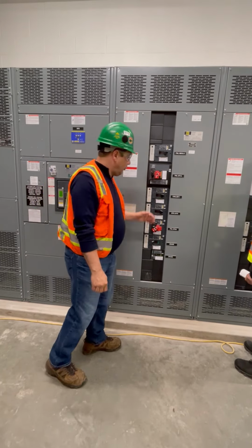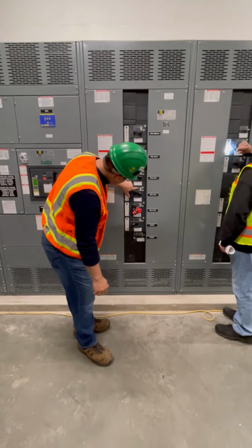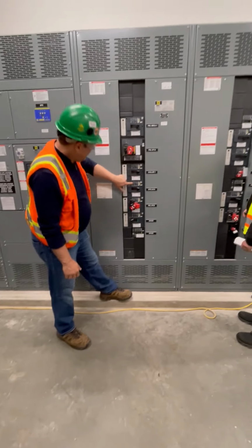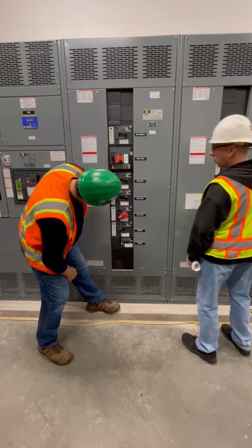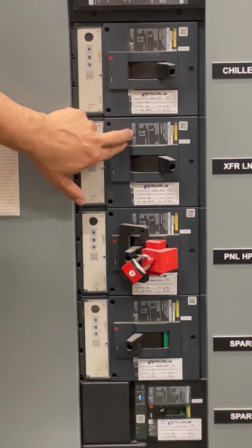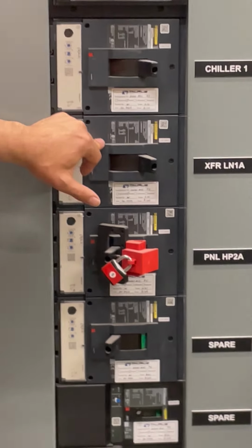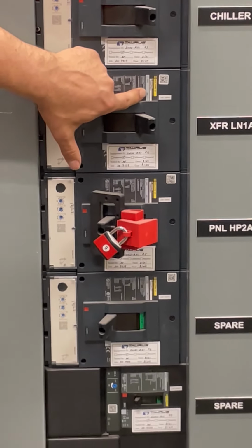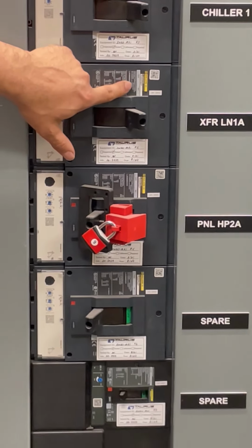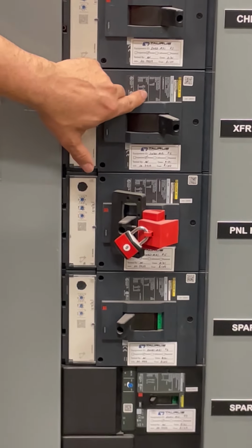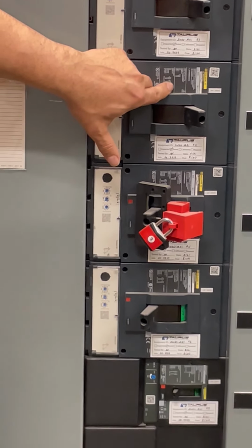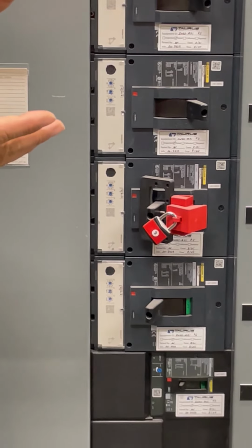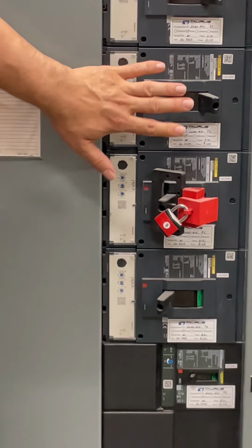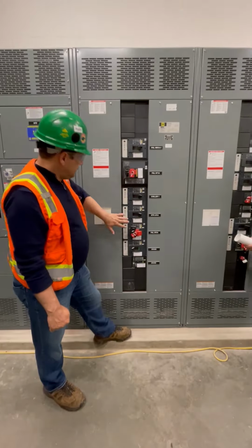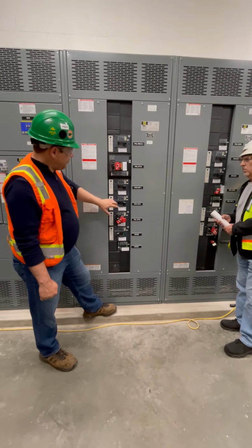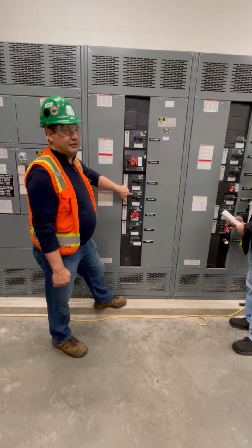But if you need to order another breaker, what you have to look at is these part numbers, right? And what you have to look at is these ratings over here. As he said before, if you have to replace a breaker, let's say I've seen customers every now and then want to upsize the load, so you go replace it from 600 to 800, which is fine as long as you order the same AIC breaker. For arc, in case there's an event going through that breaker. That's one of the most important things, the ampacities, obviously, the type of trip unit that you need, but also making sure that that breaker is rated to withstand the fault current that's going through.